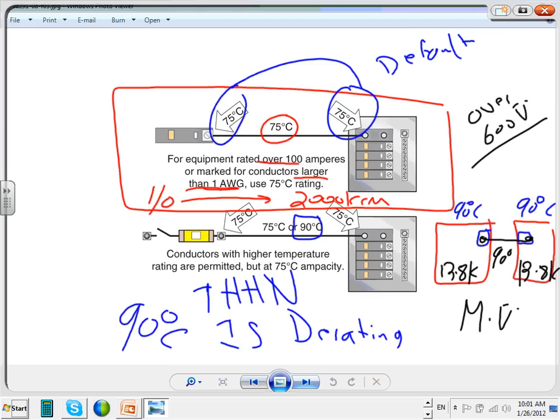Now, all of you, 99% of the time, are going to be in this application, in a commercial industrial building, using feeders with 75 rating. Only for receptacles and branch circuits do we use 60 degrees.